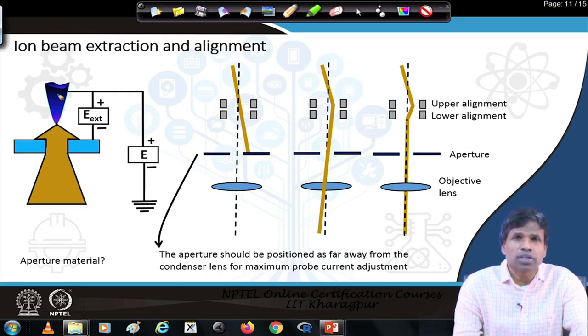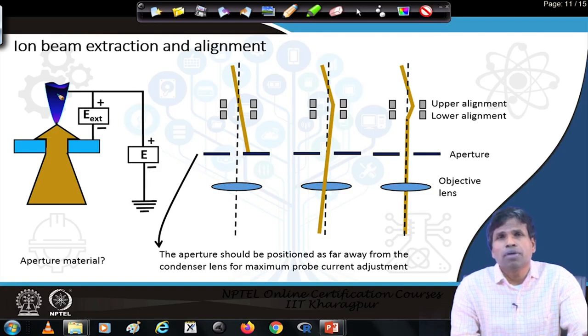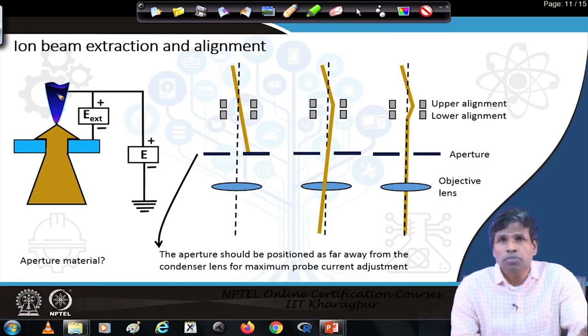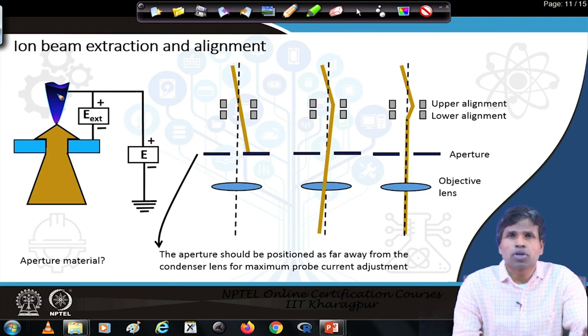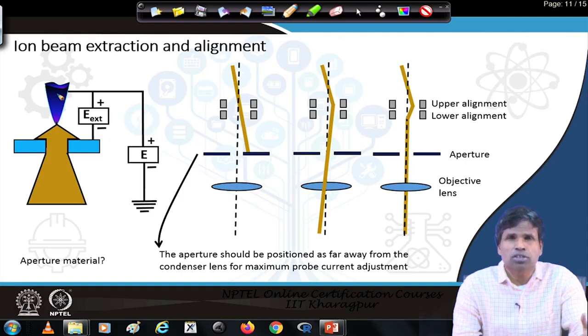The extraction voltage plays an important role in ionizing the gases. If the extraction voltage is higher, field evaporation of atoms from the tip will occur — a higher voltage would pull atoms from the surface of the tip. If we apply a lower extraction voltage, then the voltage is not sufficient to ionize the gas atoms. So an optimum voltage must be applied so that it can efficiently ionize the gas atoms at the apex of the ion source and then pull them downwards.